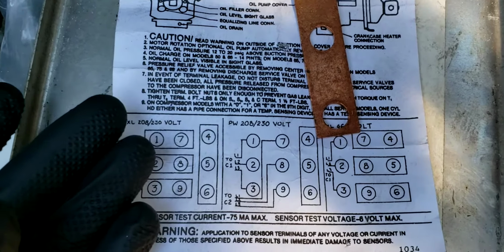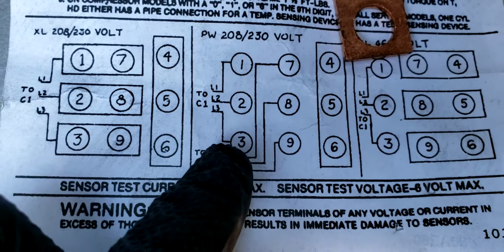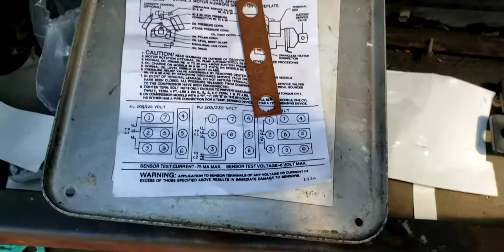Again, the 3 wires leaving contactor number 1 will go to 1, 2, and 3, and the 3 wires leaving contactor number 2 will go to 7, 8, and 9. Now, this is important. Line 1, line 2, line 3 on contactor number 1 has to correlate to line 1, line 2, line 3 on contactor number 2. What do I mean by this?